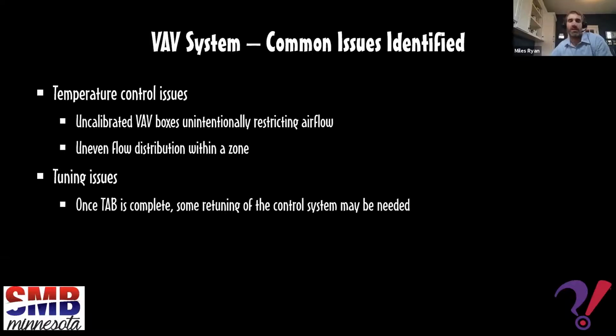Tuning issues. When a TAB professional comes in and makes adjustments, they might identify various issues that result in drastically different water flows or airflows through a system than was previously being realized. An example of this is a high-rise residential project we're working on right now, and it's a complete gut job of all the mechanical systems for the most part. They're reutilizing some existing ductwork on the makeup air unit, but for the most part, it's a complete gut job.